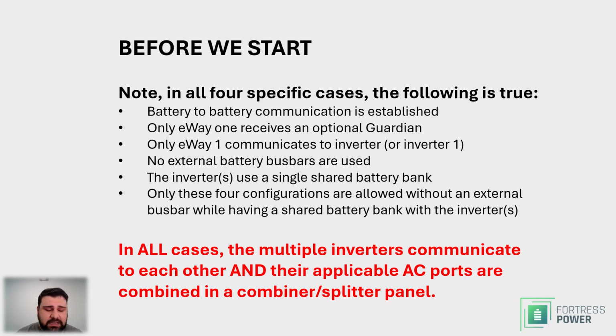So only these 4 configurations are allowed if you have no use of external bus bars, or if you're not grouping the batteries per inverter. So these 4 cases are with no external bus bars, but with a shared battery bank. So once there's a voltage from the batteries, all of the batteries and all of the inverters will see that voltage, right? Then this is this text in red.